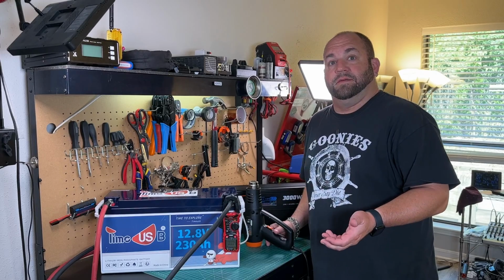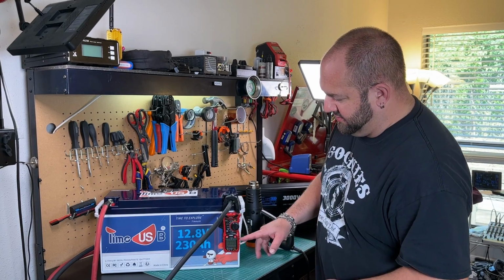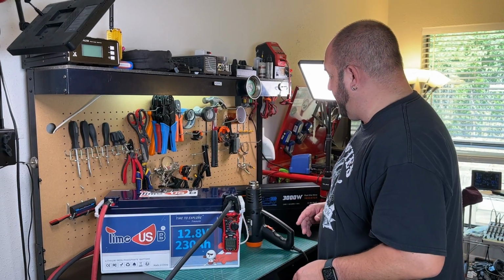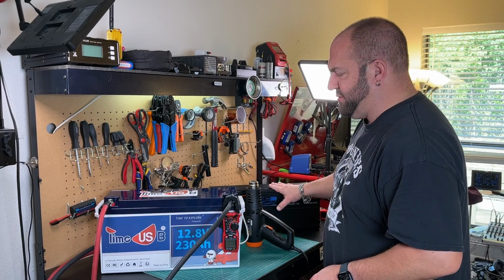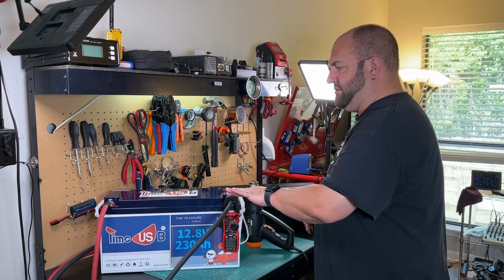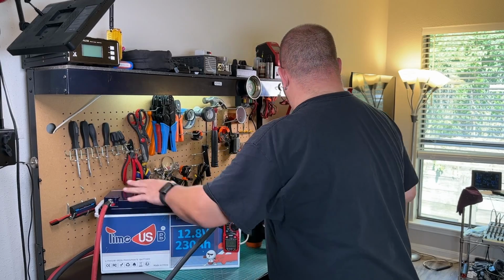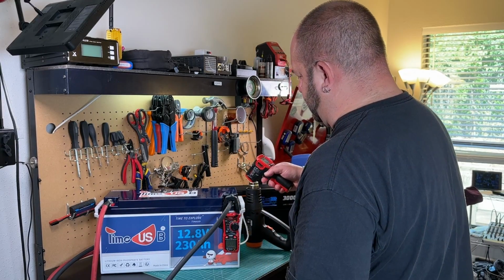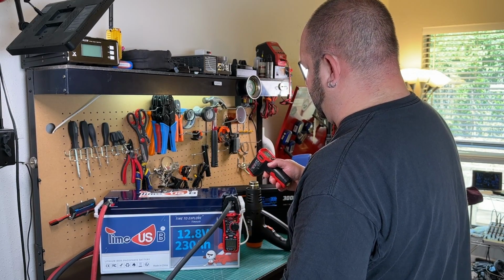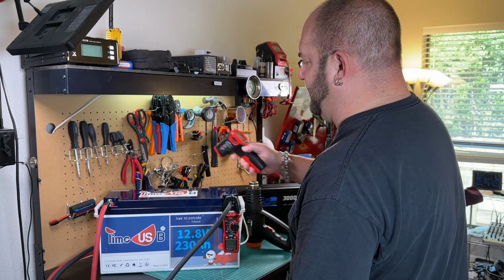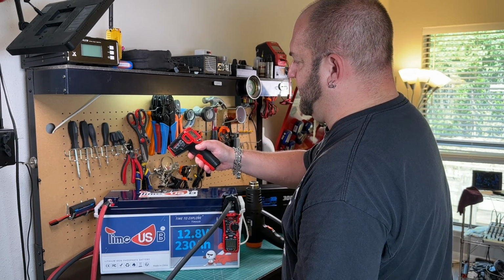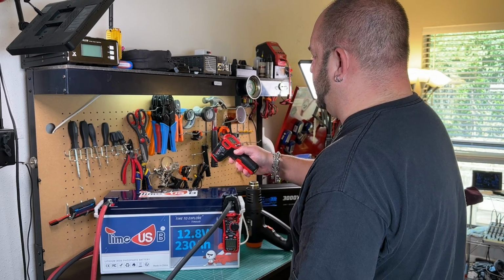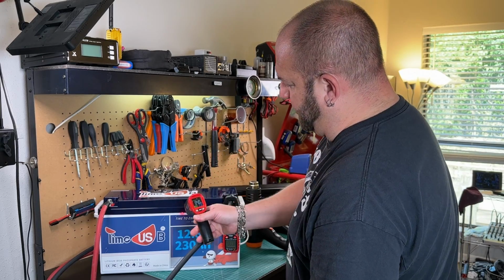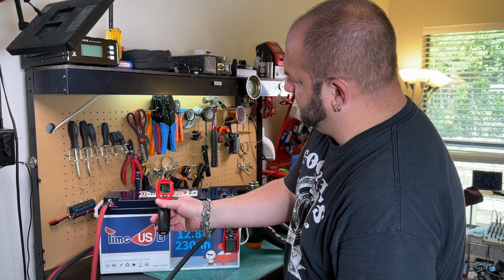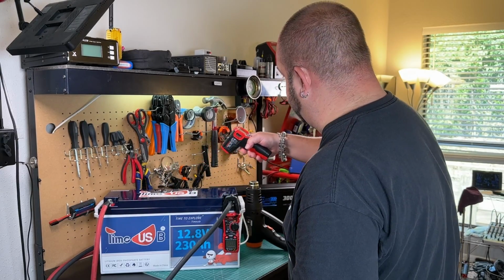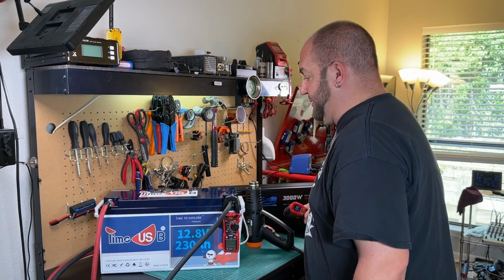It's been about 4.5 minutes now. The meter was showing a constant 121 amps being pulled, 1340 watts. The terminals are still cool to the touch, nothing's heating. Checking with the thermometer: terminals at 87 and 86 degrees, battery case about 84 degrees, 83 on the front. It's about 80 degrees in this room right now, so it handled that like a champ.